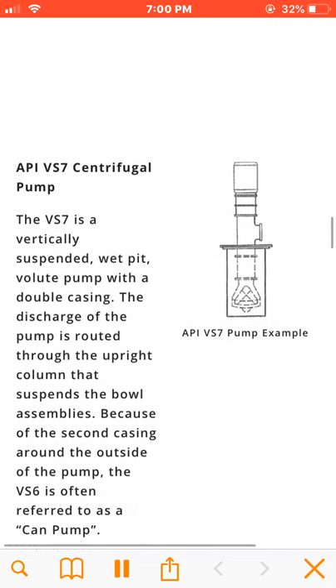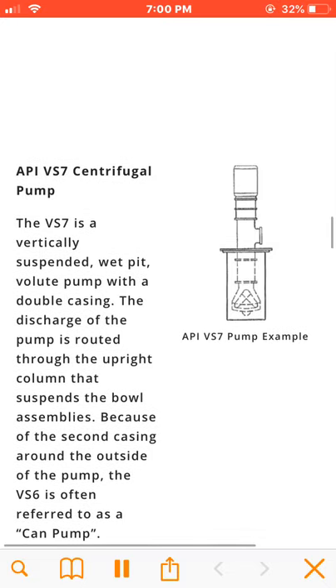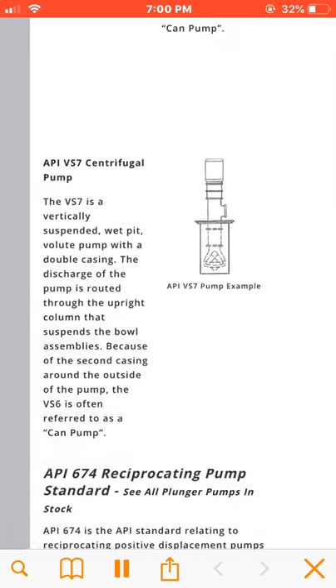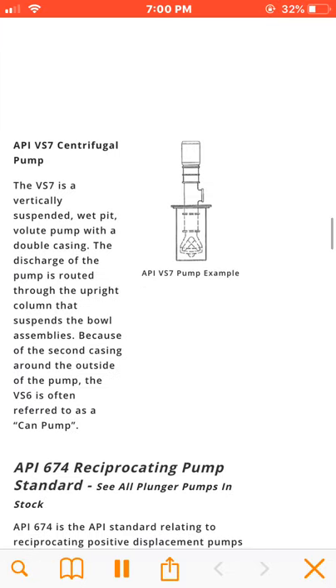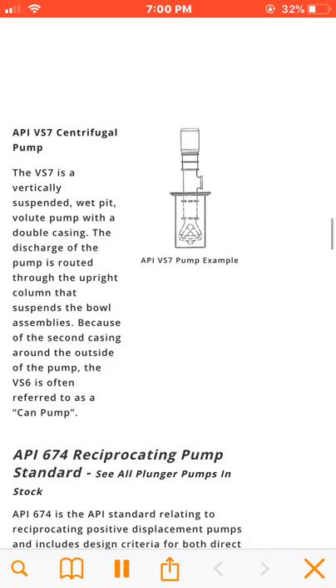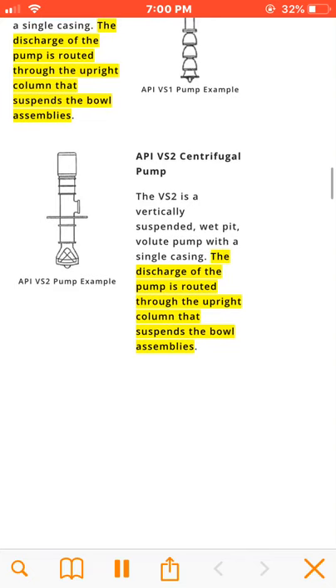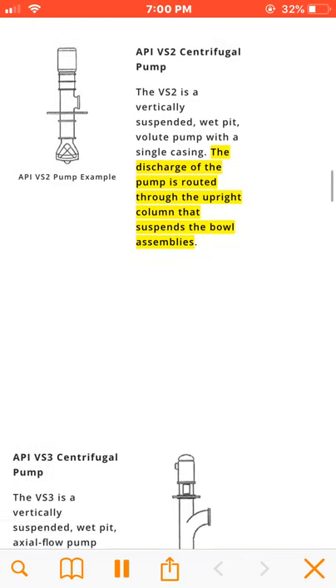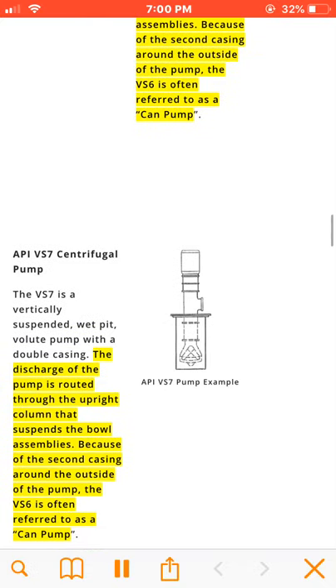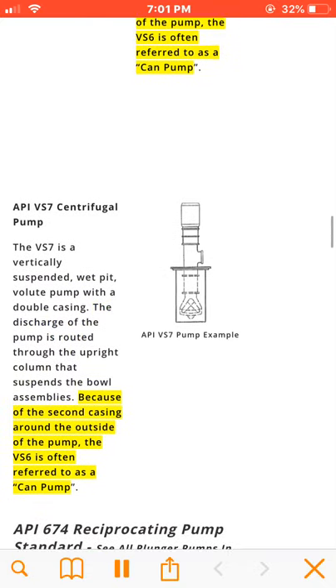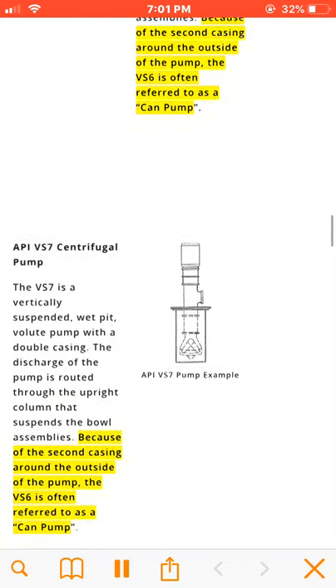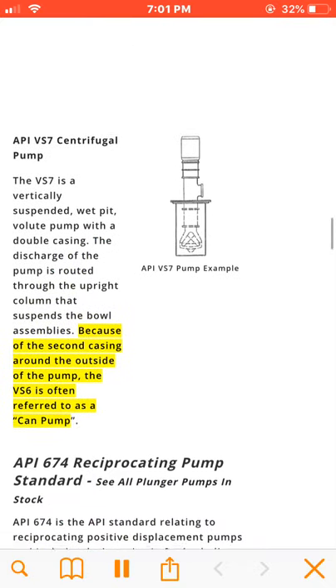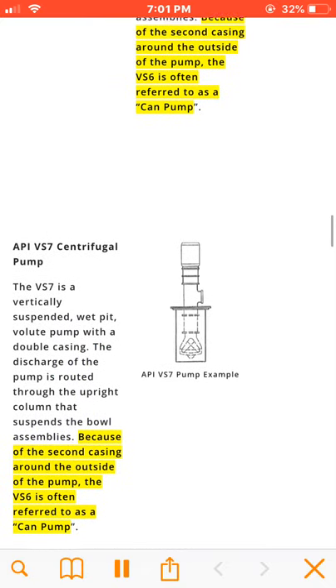The VS7 is a vertically suspended, wet pit, volute pump with a double casing. The discharge of the pump is routed through the upright column that suspends the bowl assemblies. Because of the second casing around the outside of the pump, the VS7 is also often referred to as a can pump.